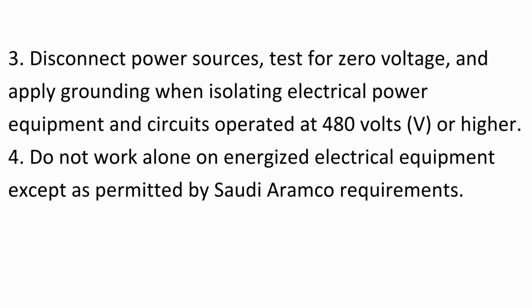3. Disconnect power sources, test for zero voltage, and apply grounding when isolating electrical power equipment and circuits operated at 480 volts, V, or higher. 4. Do not work alone on energized electrical equipment except as permitted by Saudi Aramco requirements.